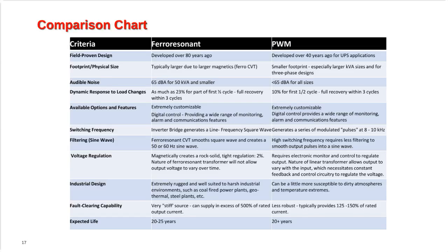Industrial design: the Ferroresonant is extremely rugged and well suited to harsh industrial environments such as coal-fired power plants, geothermal plants, and steel plants. There is very little that goes wrong with a Ferroresonant system. There aren't as many control boards, communications, or processors, although we use a processor on our new DSC Ferroresonant system. But they're just robust. They work. It's a tried and tested technology and works really, really well. PWMs, if they're designed correctly with an input and output transformer, are still well suited for industrial design, but they can be a little more susceptible to dirty atmospheres and temperature extremes. Okay, so Ferroresonants are much more suited to the industrial environment.